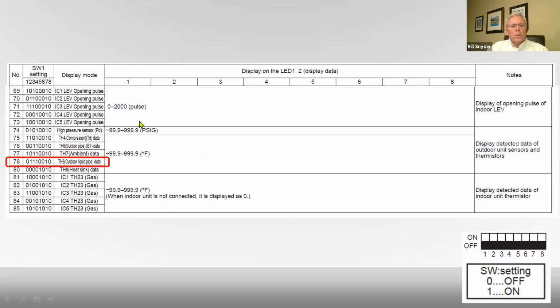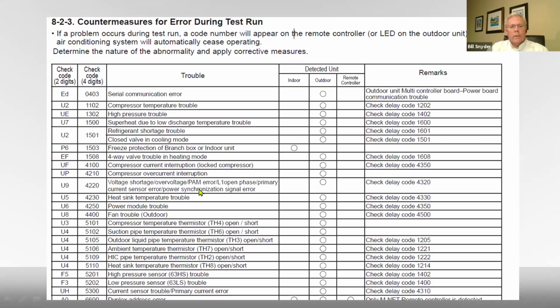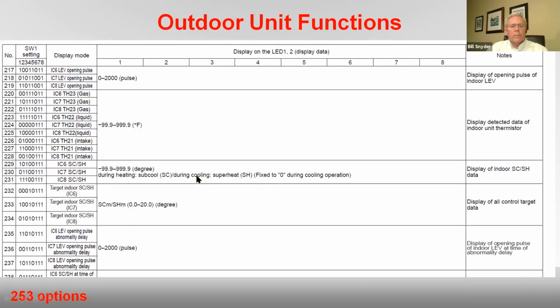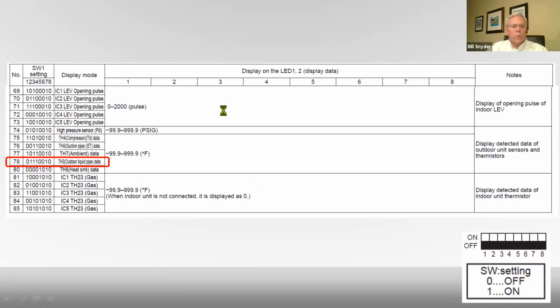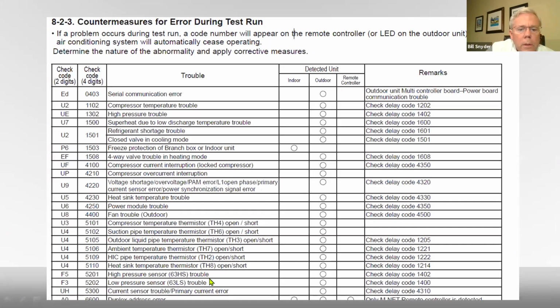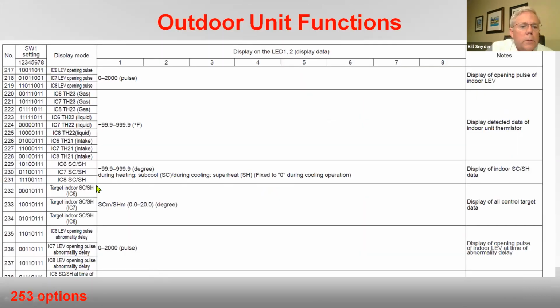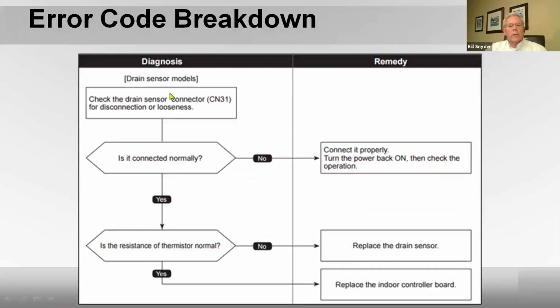You might get on one of these back here, it may say check. Let's go back. It might tell you to check your code, the CN31, connector 31 is bad. Let's see if I've got that here. I don't know if I do. I'm not seeing it here, but that doesn't mean I don't have it. No, I don't see it. But if it told you to look at connector 31, you go to these diagrams and it says check the sensor. Is it plugged in? Does it look tight? Yes. Then you go down here. Is the resistance of the thermistor normal? Yes or no? You look at the drain pan sensor rating and see if it was open or closed or shorted, and it would tell you if it was good or bad.